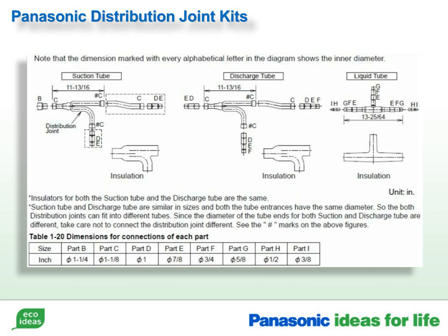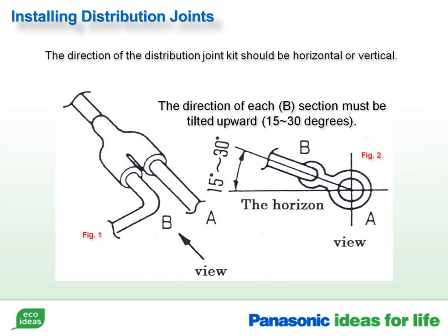You should only use Panasonic supplied distribution kits. Part numbers and locations will be on the piping diagram. They come with formed insulation which cannot be ordered separately, so be careful not to lose them. If you do misplace them, you could create your own with sheets of insulation. The distribution joints should always be installed in a vertical or horizontal position, and have a pitch of 15 to 30 degrees of rise on the long radius 90.